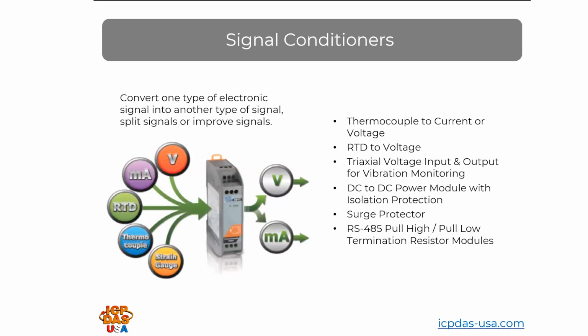Signal conditioners convert one type of electronic signal into another type of signal. They're also used to improve or split signals. We offer different types. Some of them take thermocouple temperature measurements and then convert those into current or voltage. Some of them take in temperature RTD and then turn that into a corresponding voltage. We also have triaxial voltage input and output modules for vibration monitoring.